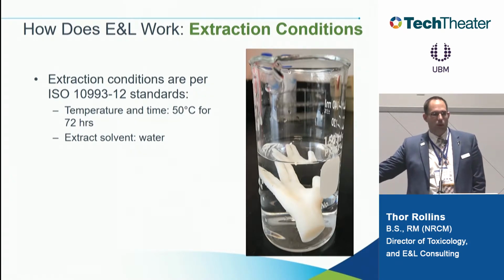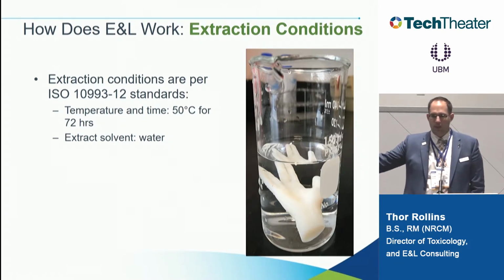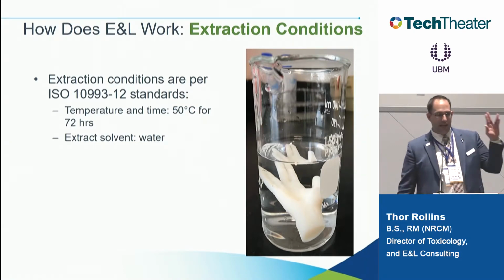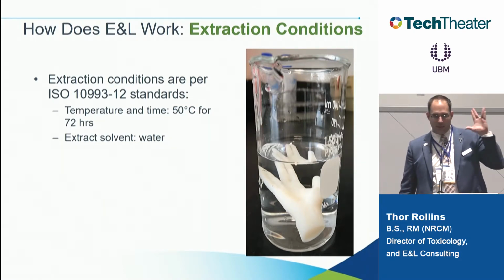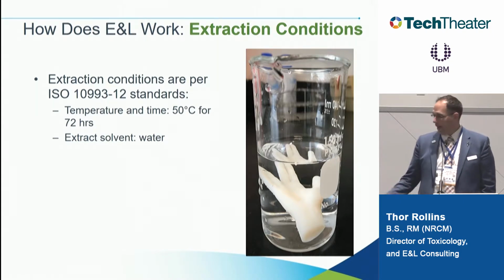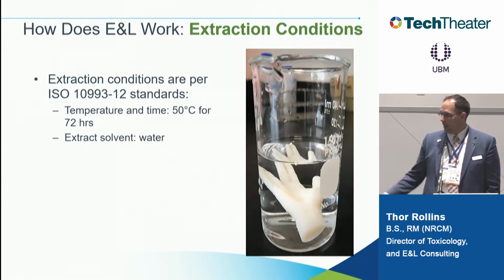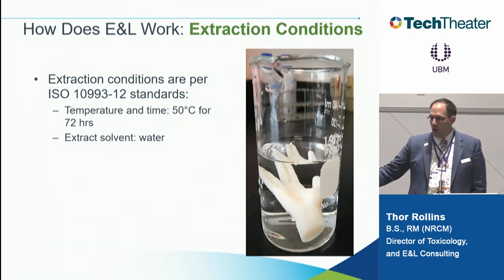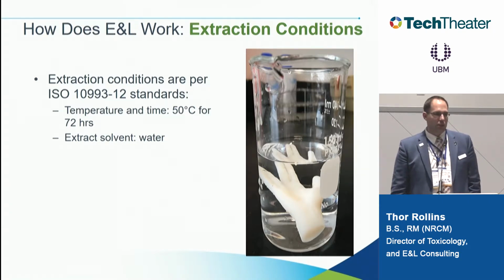So this is our typical extraction. Once again, this is just an example of a -18. I would run the water through the gas path, but this one, we extract the whole device into the water. I don't know if you can see that, but that's Leonard Nimoy's Star Trek hand, okay? So we extract it in water. We recommend a clinical aggressive extraction. We do have up here 50 degrees C for 72 hours.